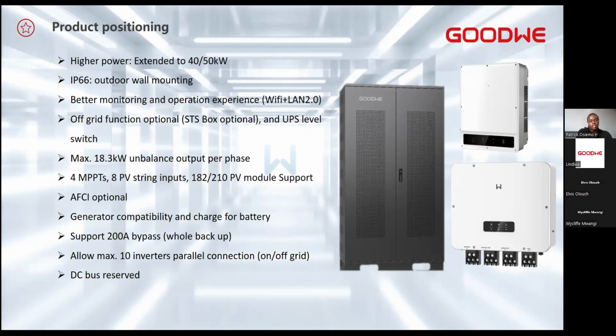You can parallel this installation. One inverter, taking the higher end, is 50 kilowatt. You can do up to 10, so 500 kilowatt AC. Each inverter can handle 3 banks of the Lynx C. So 3 banks, taking the higher end, will be 156 kilowatt hour. So a single ET inverter, 50 kilowatt, can hold 468 kilowatt hour of battery. If you do that for 10 pieces, you have 4.6 megawatt hour. That is big. It is enough to power a community or a hospital. We have cases with hospitals or schools.